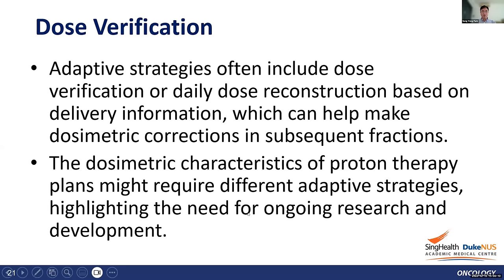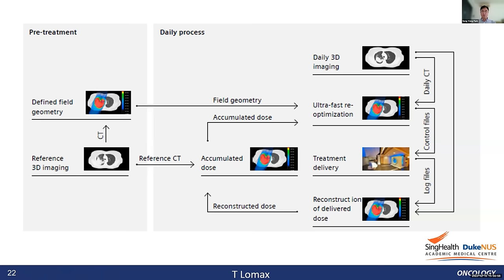This is a typical workflow for online adaptive therapy with in-room CT. From a pre-treatment stage you generate a plan from reference 3D imaging. On each daily process using in-room CT, you compare the daily imaging, perform ultra-fast re-optimization and dose calculation, and deliver the treatment beam to the patient. From the log file you reconstruct the delivered dose to calculate accumulated dose, ensuring what dose will be expected for this patient.